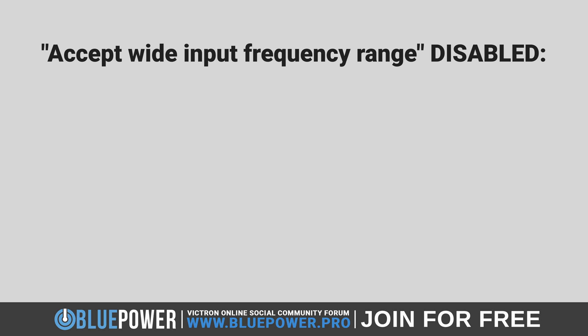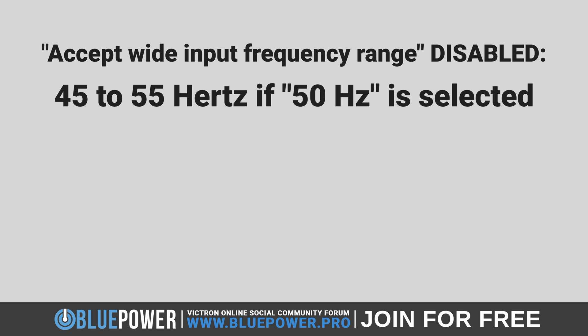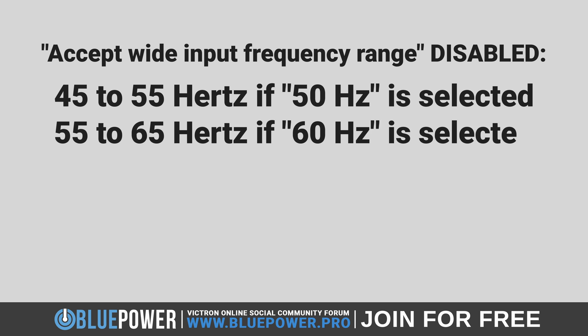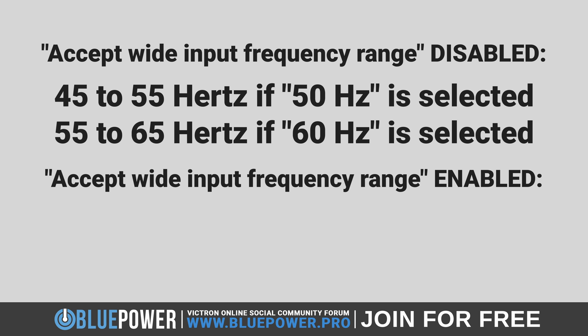So, depending on your choice, this ranges from either 45 to 55 Hertz if 50 Hertz is selected, or 55 to 65 Hertz if 60 Hertz is selected. Conversely, if the Accept Wide Input Frequency Range setting is enabled, it combines these two frequency ranges, allowing for a frequency range all the way from 45 to 65 Hertz.